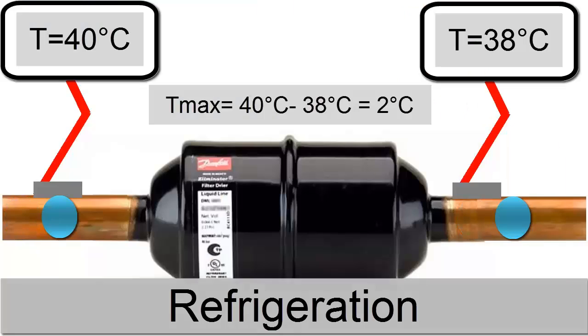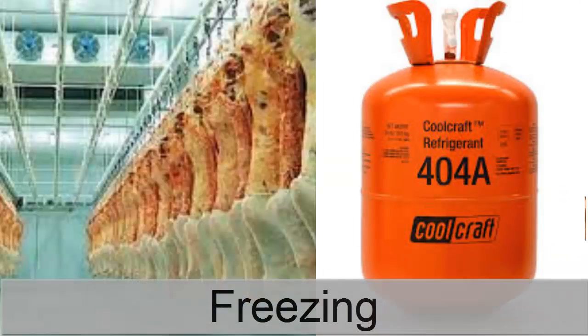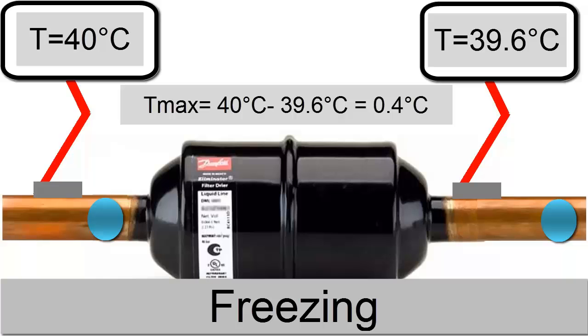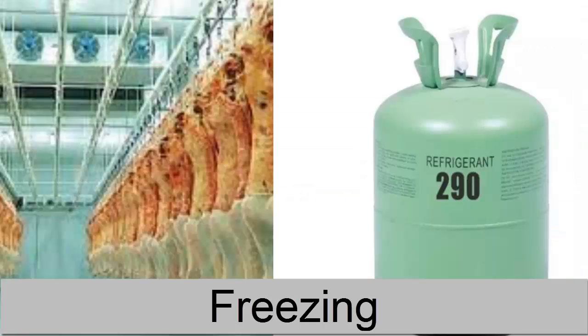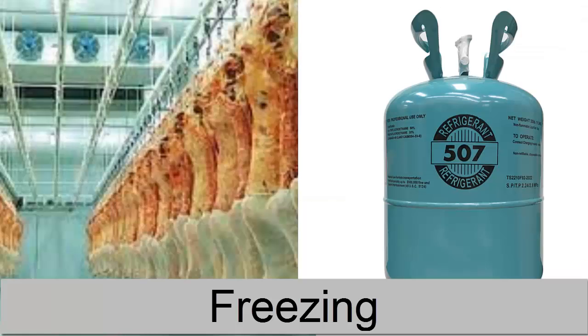In the case of freezing systems with R-404A gas, the temperature drop indicating obstruction is 0.4 degrees Celsius. With R-290, the temperature drop is 0.5 degrees Celsius. And for R-507, the temperature drop is 0.4 degrees Celsius.